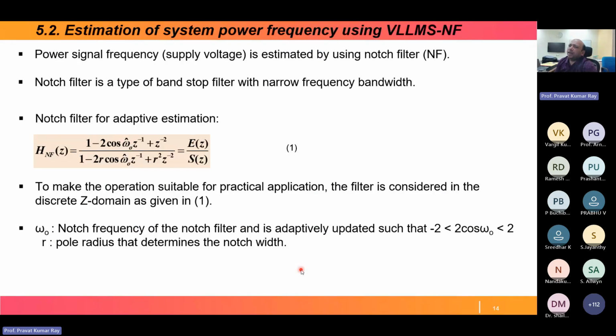Next is the accurate estimation of power system frequency using the variable leaky least mean square algorithm in combination with a notch filter. The notch filter is basically a type of band-stop filter with a very narrow frequency bandwidth, and its transfer function is given in equation 1, where omega-0 is the notch frequency, updated adaptively, and R gives the pole radius, since the notch varies depending on different values of R.